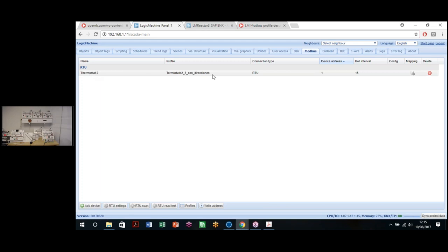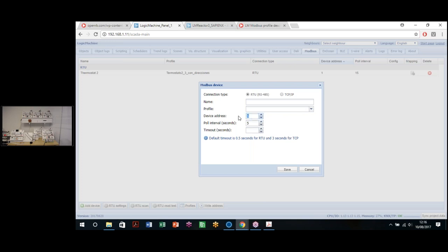Once we save, the information has been uploaded to this list, and we can see here that we have an RTU device with this configuration. The other way that we can add a device is using the Add Device button. If we already know the address of that device, we can set it right here. And of course, we can add a TCP/IP Modbus device. If we click on TCP/IP, it will change some options and it will ask to insert the IP and the port of that specific device. And that's the only difference.